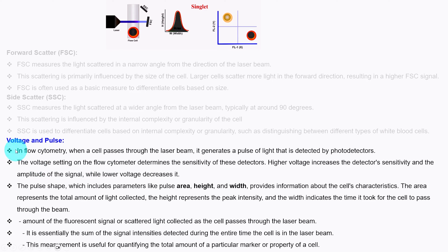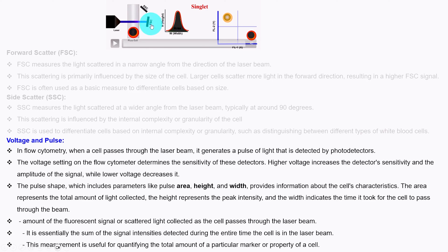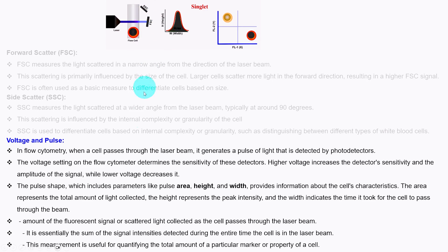The third important parameter is voltage and pulse. In flow cytometry, when a cell passes through the laser beam, it generates a pulse of light that is detected by the photodetectors. The voltage setting on the flow cytometer determines the sensitivity of these detectors — higher voltage increases detector sensitivity and the amplitude of the signals, while lower voltage decreases it. Pulse shape is a very important topic, which includes parameters like area, height, and width.